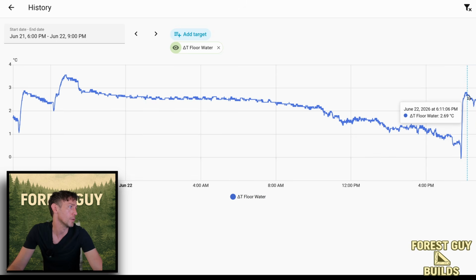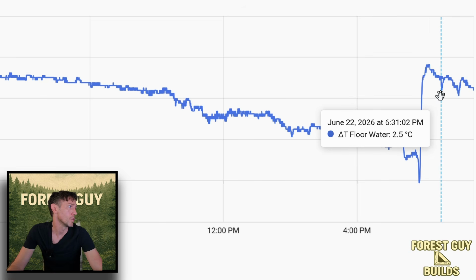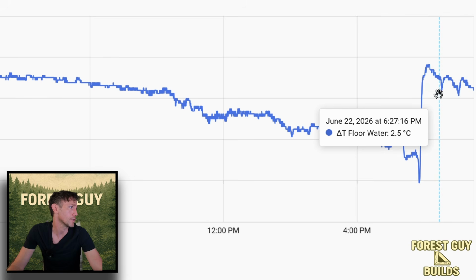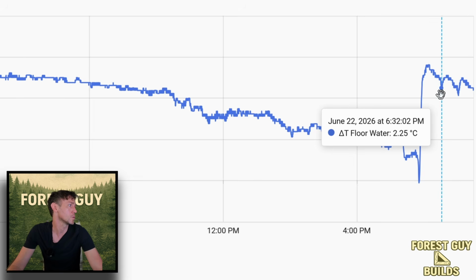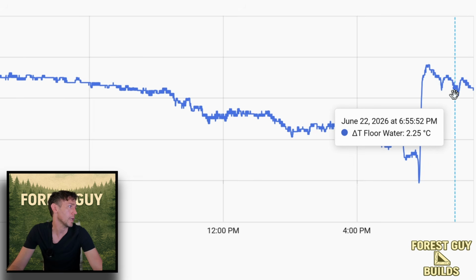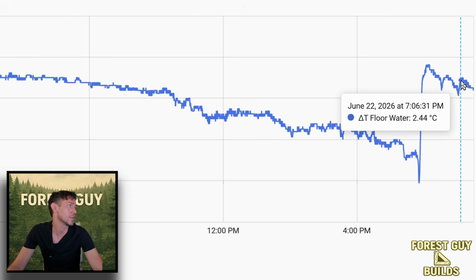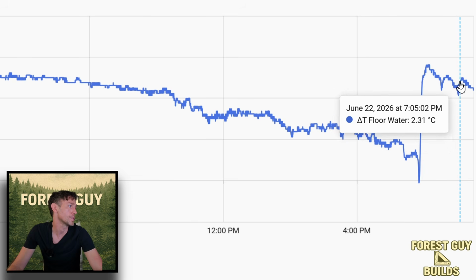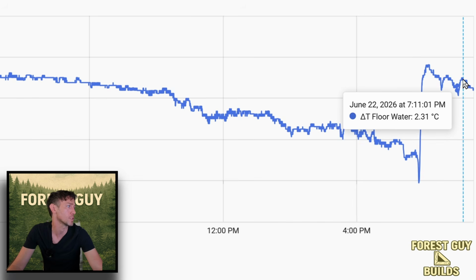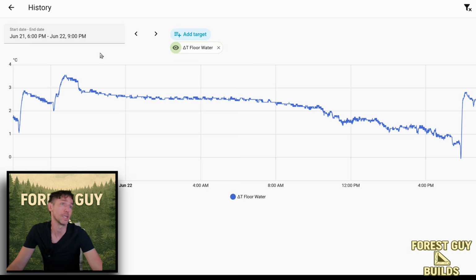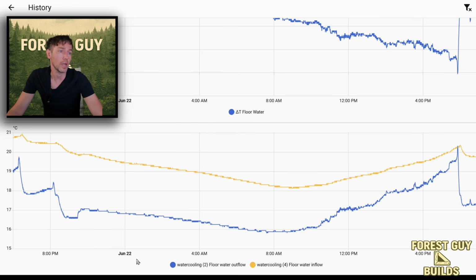After those adjustments, we went back to almost 3 degrees delta. Those dips are interesting too, and we can easily explain them: fresh groundwater floods into the buffer. Every 30 minutes new groundwater gets pumped into the buffer, which gives a new supply of cold water and more cold energy transfer to the floor cooling. The graph I showed with the delta is the result of those two temperatures, the inflow and outflow of the floor cooling circuit.